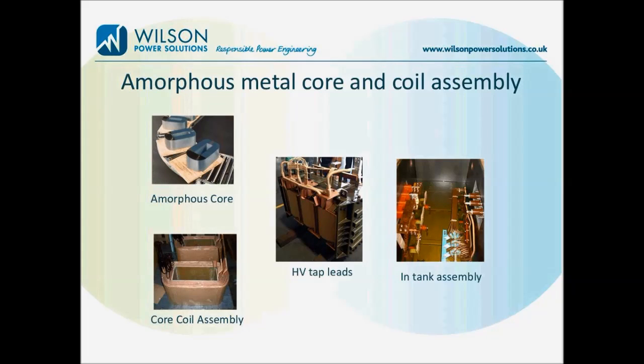Amorphous core assemblies are actually very short and fat in appearance compared to a standard construction. So you might think that it's a waste of oil there, that top expansive tank with oil in it. But actually, the reason we did that was that we were meeting IEC standards upon design and cable heights of the transformers. So that when you're retrofitting a transformer you can swap one out for the other and use your existing cable boxes.